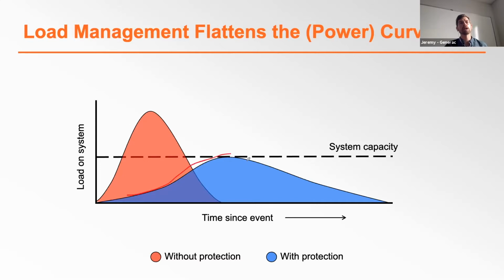When you have load management in your system, you prevent it from exceeding system capacity, you can run longer, and you won't encounter a potential brown or blackout scenario. Rather than overbuild a system to meet a capacity level you're not going to see that often, we can use load management to intelligently control and sequence the way loads turn on. When we manage loads, we ensure there's always capacity for the highest priority loads. You can see the big difference on the graph between a system that involves load management, in blue, and one that does not.